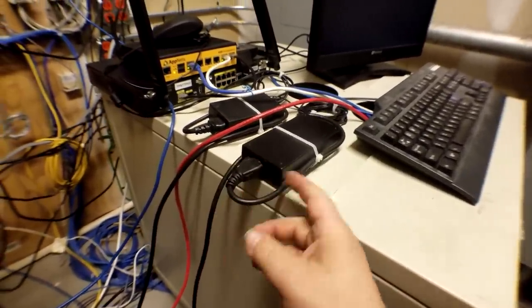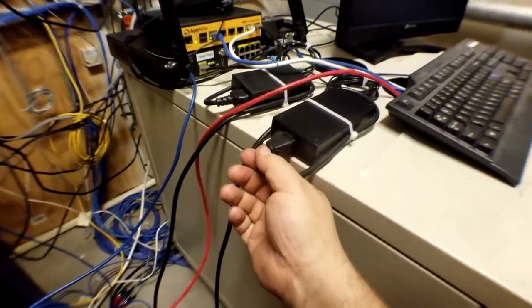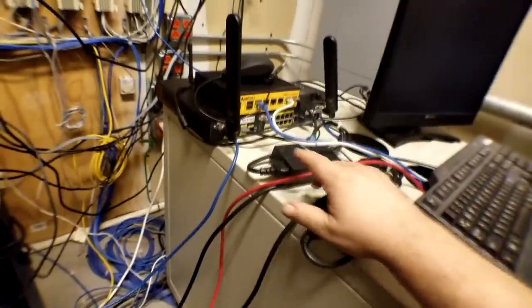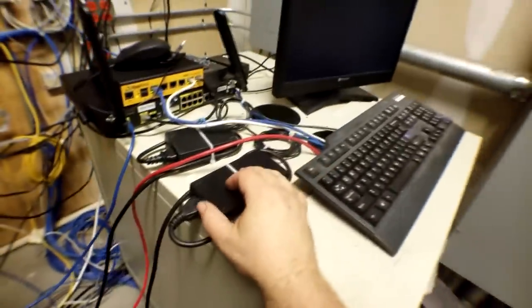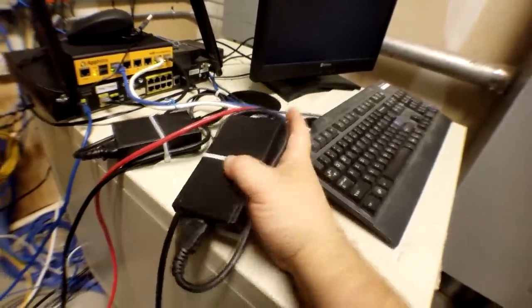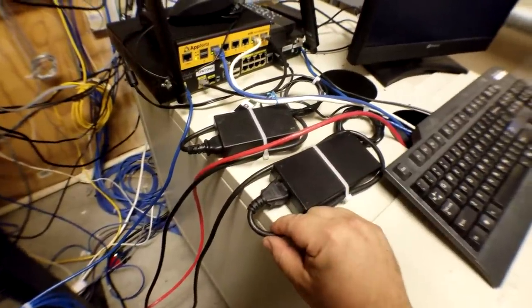In many cases the power bricks were either zip-tied to the side of a rack with the power cable holding in by friction alone and fighting against gravity, or they were just dangling across the back. Several pieces of equipment did go down during this cleanup process — we found them on the floor with the plug slightly loose and disconnected. A practice I've started is securing these so the thing can be tugged on or stepped on and you're not going to risk having that AC plug yanked out.